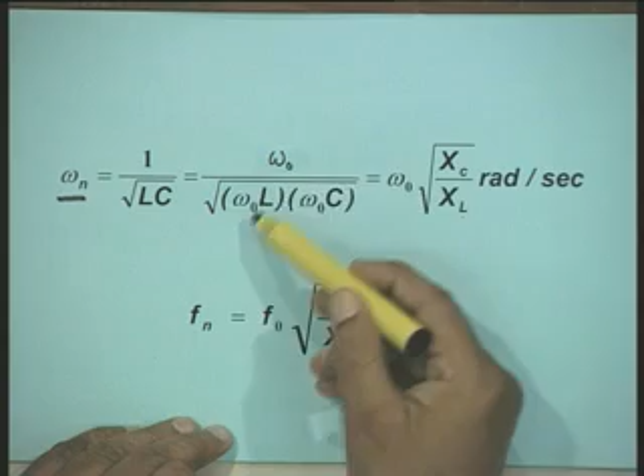This can be written as omega naught divided by the square root of omega naught L into omega naught C. This is exactly the same, since you have multiplied and divided by omega naught. This can be expressed as omega naught multiplied by the square root of Xc by XL. Therefore, we now have a relationship between the natural frequency of oscillation fn and the system frequency f0, and the values of the line reactance and the reactance of the series capacitor. This relationship is a very important one.